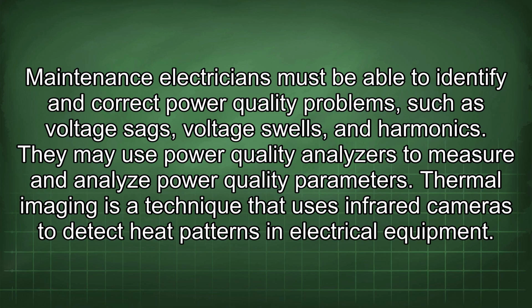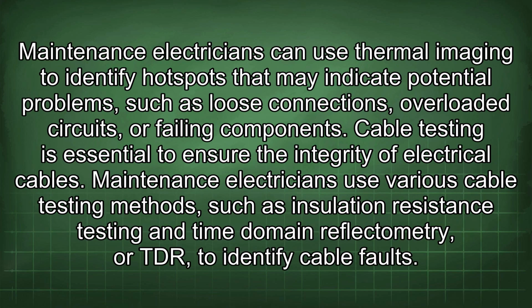Thermal imaging is a technique that uses infrared cameras to detect heat patterns in electrical equipment. Maintenance electricians can use thermal imaging to identify hotspots that may indicate potential problems such as loose connections, overloaded circuits, or failing components. Cable testing is essential to ensure the integrity of electrical cables. Maintenance electricians use various cable testing methods such as insulation resistance testing and time domain reflectometry, or TDR, to identify cable faults.